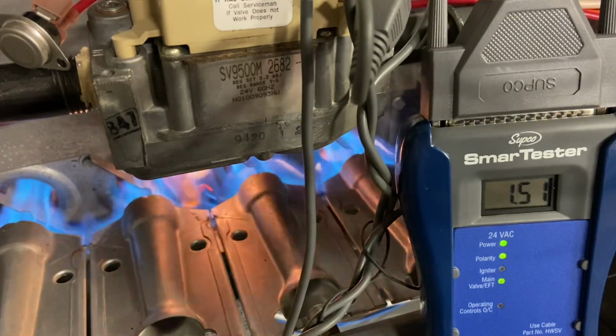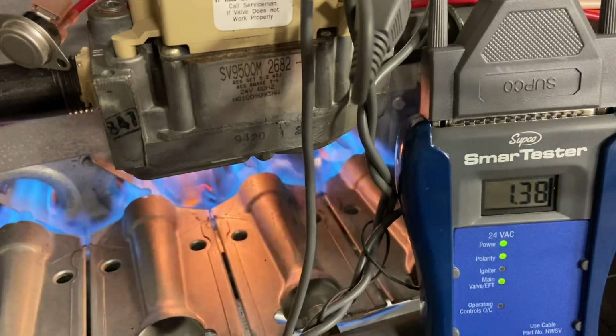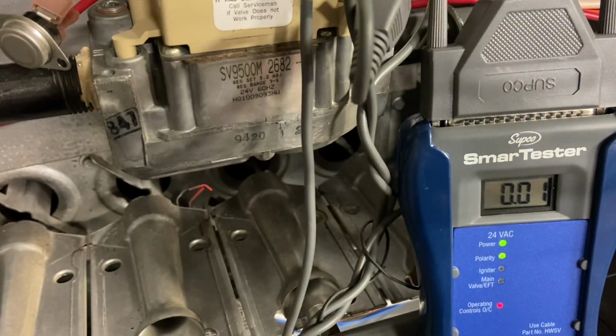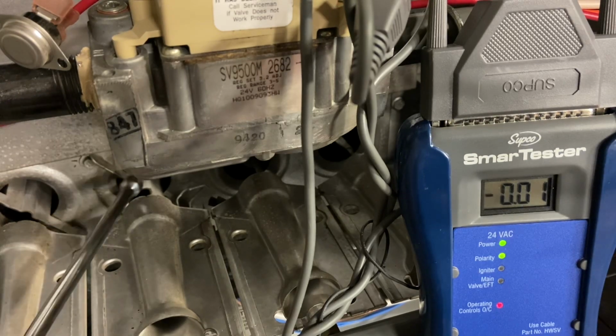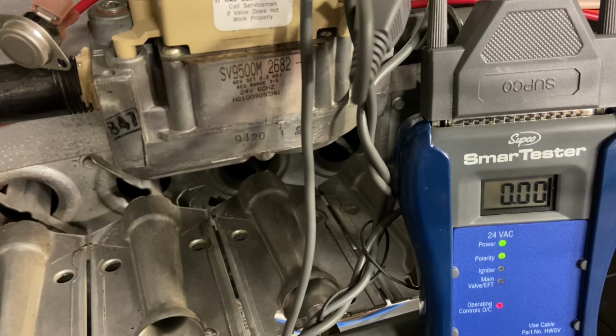So I'm going to end the call for heat by removing R and W. We can see that everything shuts off immediately. You can also see that our red light came on saying that we do not have our call for heat. So that's our system. It's pretty simple, it's pretty basic. This particular unit has these diffusers inside the heat exchanger, and you'll see that more on propane systems, but it's designed to spread the flame out and just transfer heat better. It's just some of the different technologies that were used.